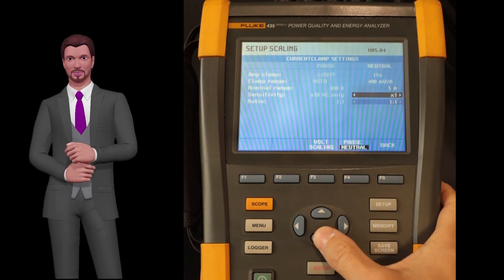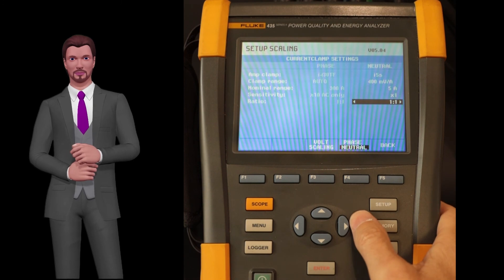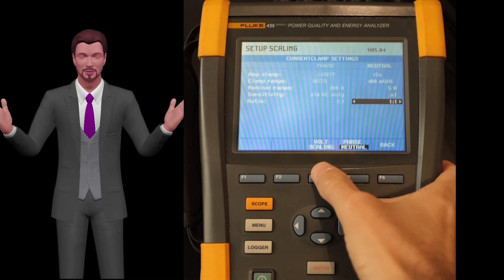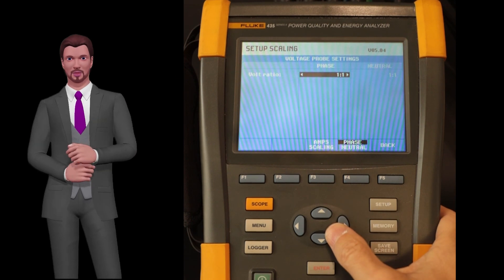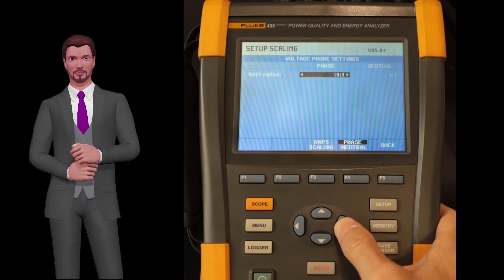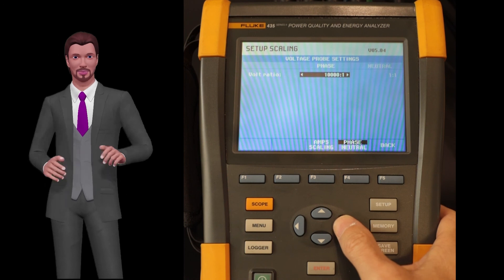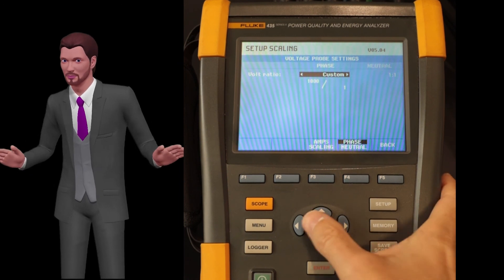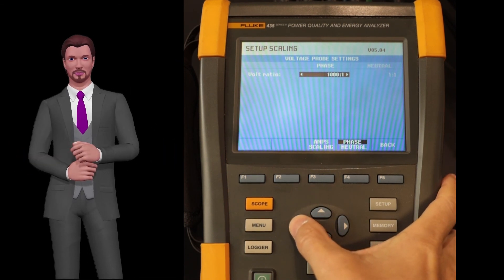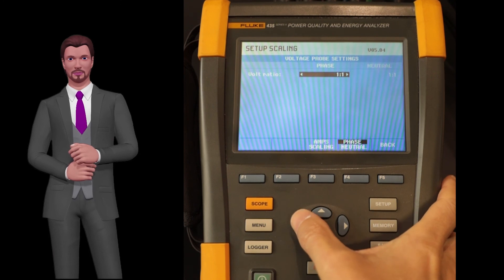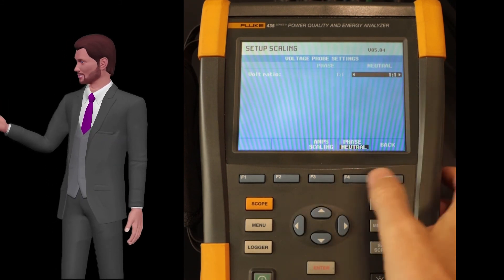Once the current probes have been configured, by pressing the F3 key we can also configure the ratio for the voltage measurement transformers if we are in a medium or high voltage installation. Again with F4 we can separately configure the phase voltages and the voltage between neutral and earth. Both voltage and current ratios should be set to a 1 to 1 ratio if working in a low voltage installation.